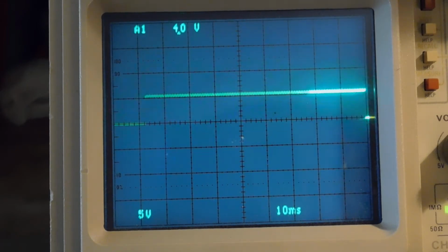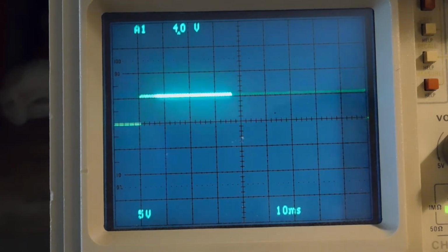The D gain isn't going to do anything because there's no rate of change in the pressure. So we can prove that by setting the D gain to 1, and I don't think anything will happen. No, nothing happens. Okay, so we're going to set the D gain back to 0. That's how the math works in the PID loop.